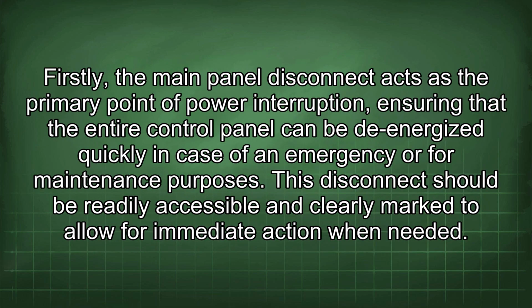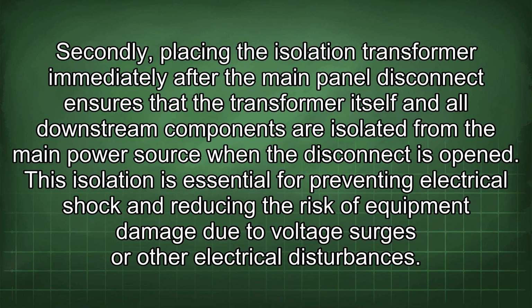Firstly, the main panel disconnect acts as the primary point of power interruption, ensuring that the entire control panel can be de-energized quickly in case of an emergency or for maintenance purposes. This disconnect should be readily accessible and clearly marked to allow for immediate action when needed. Secondly, placing the isolation transformer immediately after the main panel disconnect ensures that the transformer itself and all downstream components are isolated from the main power source when the disconnect is opened. This isolation is essential for preventing electrical shock and reducing the risk of equipment damage due to voltage surges or other electrical disturbances.